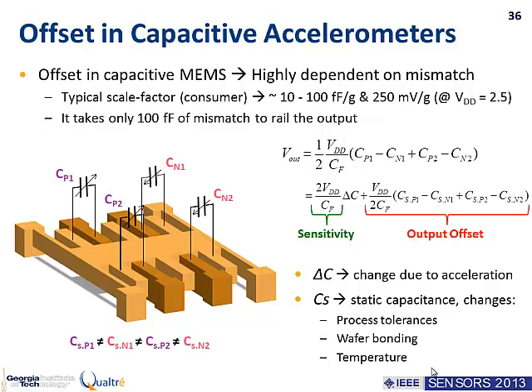Yeah, obviously there are limitations associated with this type of calibration. If, for example, the gap between the electrode that you're using to produce that force changes differently than the gap that you use to sense your acceleration, then you're going to have an error associated with that. But generally these errors are going to be much smaller than what you're trying to calibrate for, so there are definitely limitations to the technique.